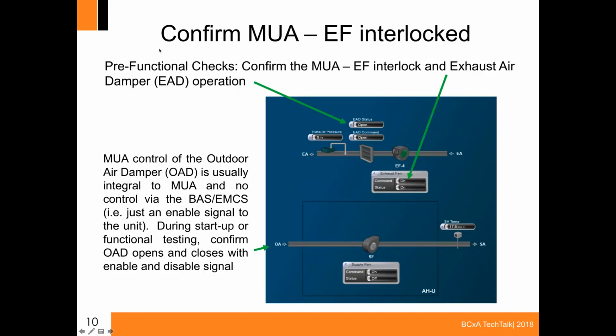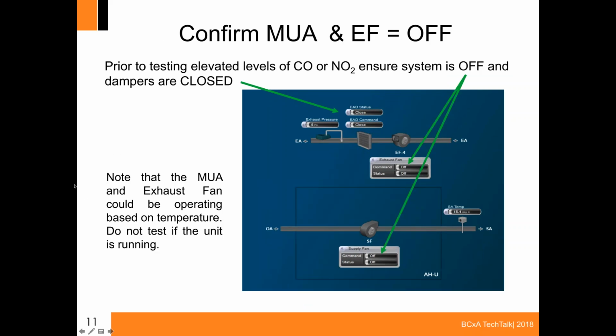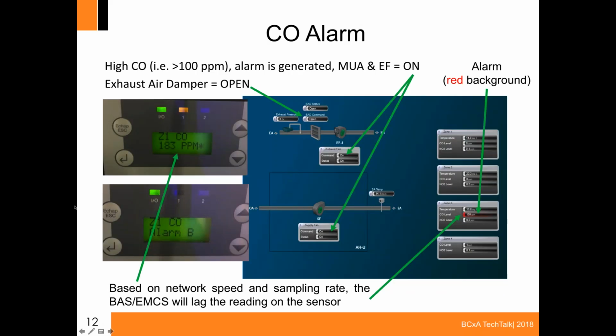Once it goes to the makeup air unit, this is usually an internal control that the controls contractor has no control over. He can only enable. So you have to make sure that the outdoor air damper opens and then the supply fan starts. Otherwise, you will not be bringing in outdoor air. Because we get very, very cold winter temperatures, this unit could be running already because it's trying to keep the temperature in the parking garage, which we try to keep at about 45 Fahrenheit or just over 7 degrees Celsius. So as I said, make sure that this is all off. The system is completely off and the dampers are closed prior to your testing. And then I went through the sequence of what happens as it does go. So we made sure that this was all shut down and not operating for either gas or the temperature set points.